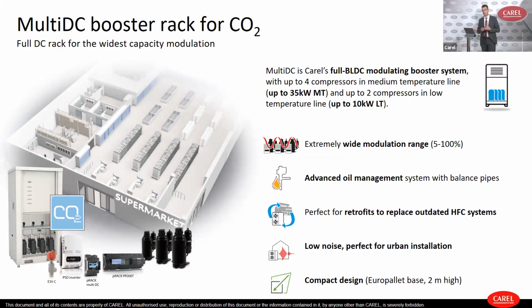So an extremely wide modulation range that you cannot match with other units on the market. Of course, this solution is completed by an advanced oil management that we will see in the next slide. And it is really perfect for retrofits of old HFC units, especially in urban installations, because this solution has very low noise compared to the semi-hermetic reciprocating compressor solutions. And it is very, very compact.